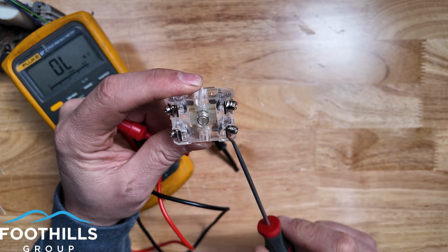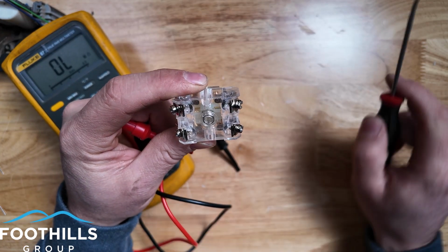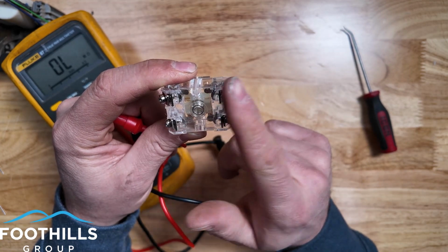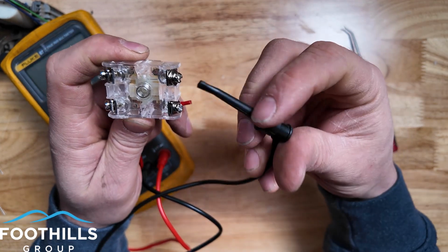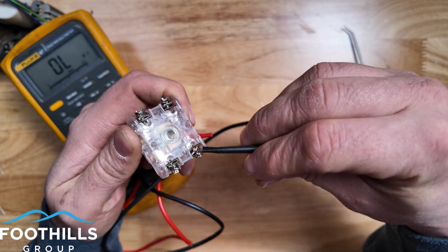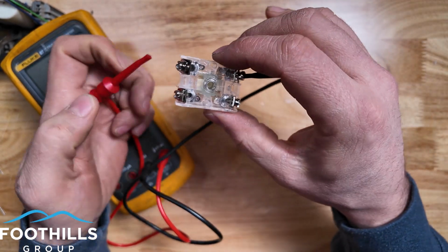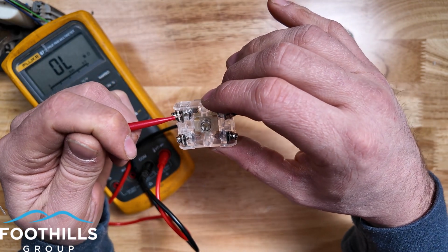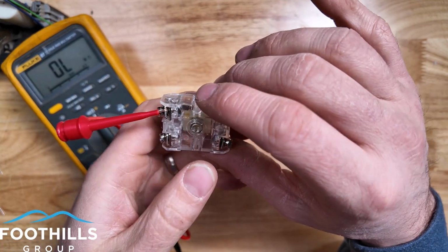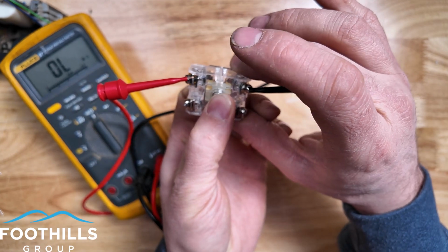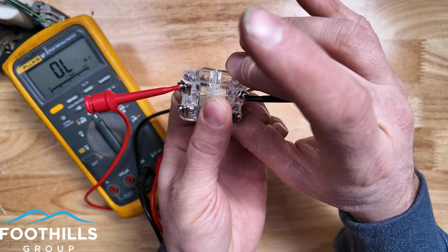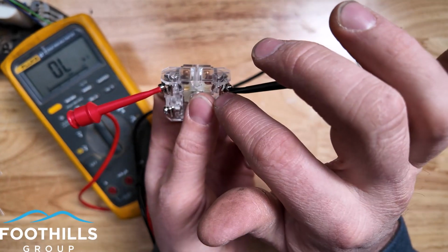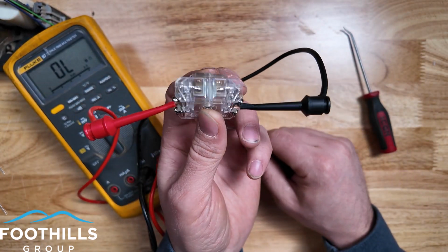So this has one circuit here and one circuit here being controlled. And when you push the one button, both circuits are complete. And we have isolation from one circuit to another. That's something you'll also want to make sure you check when you're working with multi-pole circuits, that you don't have a short happening inside, a wire-to-wire short. So even when I push the button or not push the button, we don't have continuity from terminal to terminal across this switch, and that is what we would expect.